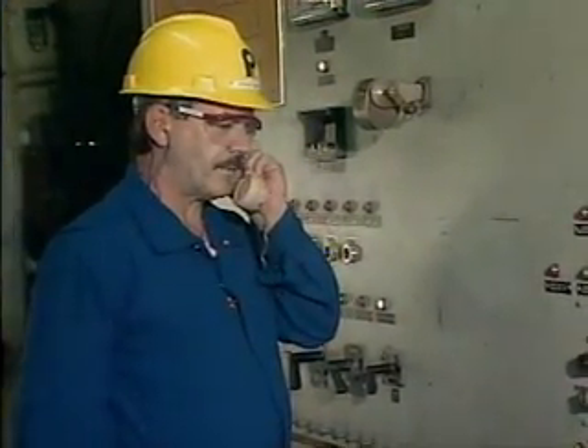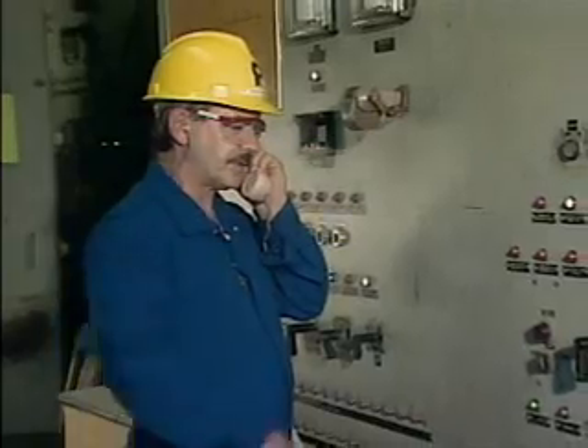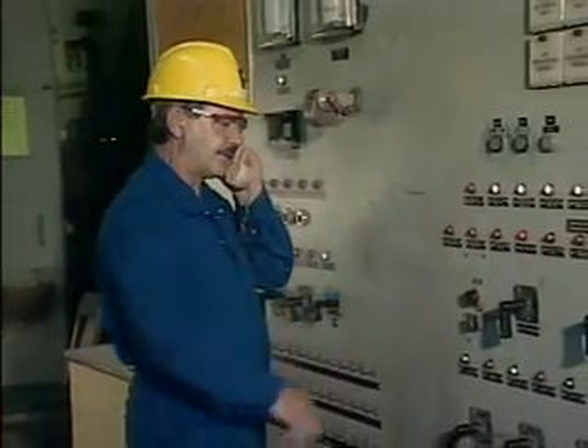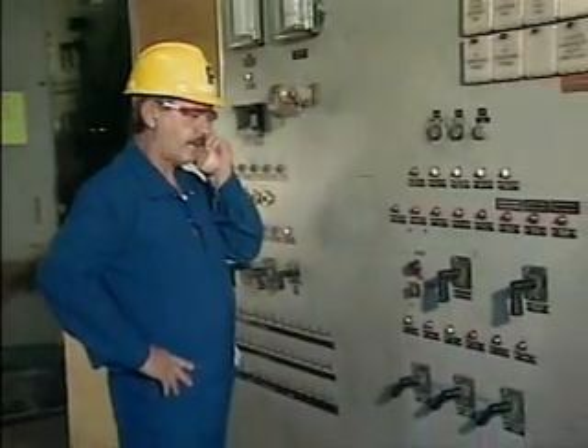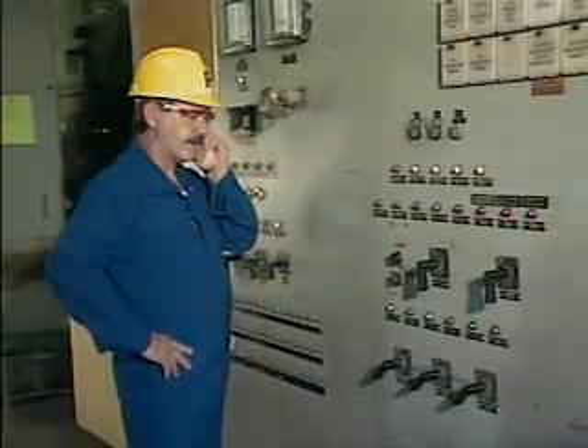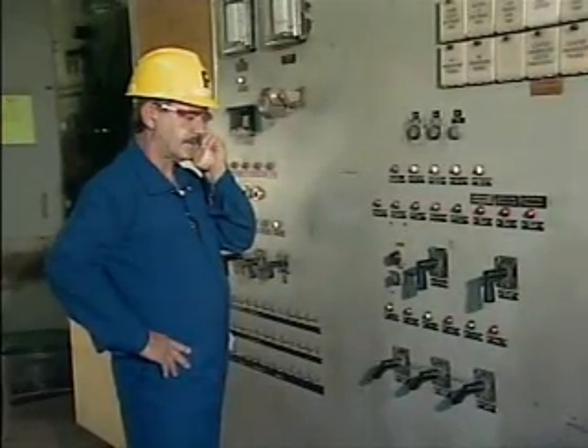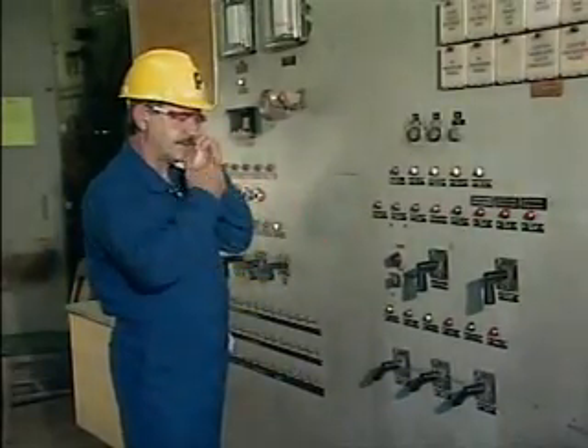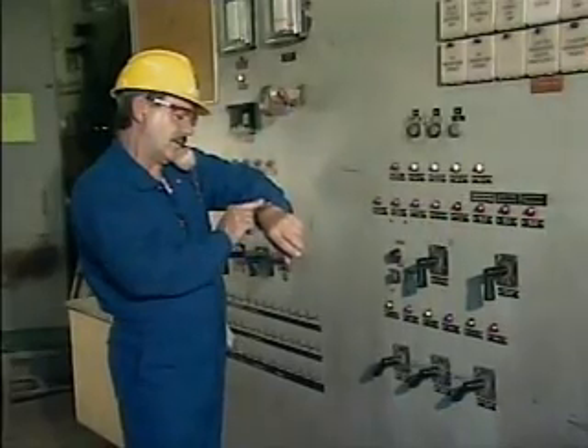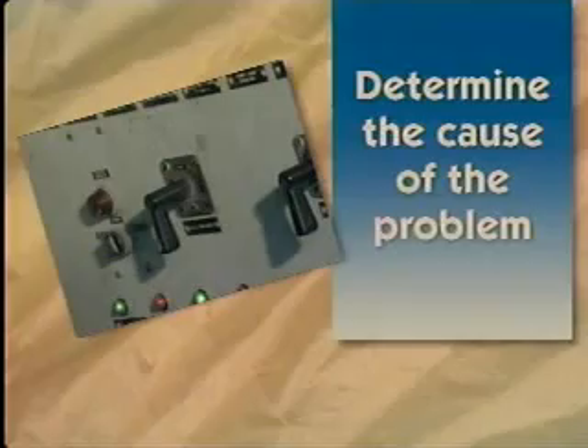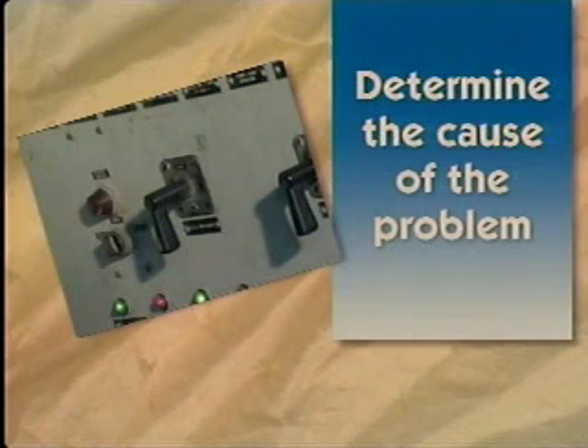In this case, he talks with the appropriate personnel working in the affected units. He lets them know what he'll be doing, and he finds out that repairs have already been started on the problem in the B silo. With that silo out of service, he's told that in about 30 minutes other workers will have to begin shutting down the boilers. Having informed personnel in units that are affected by this problem, the electrician focuses on the next basic troubleshooting step, which is to determine the cause of the problem.